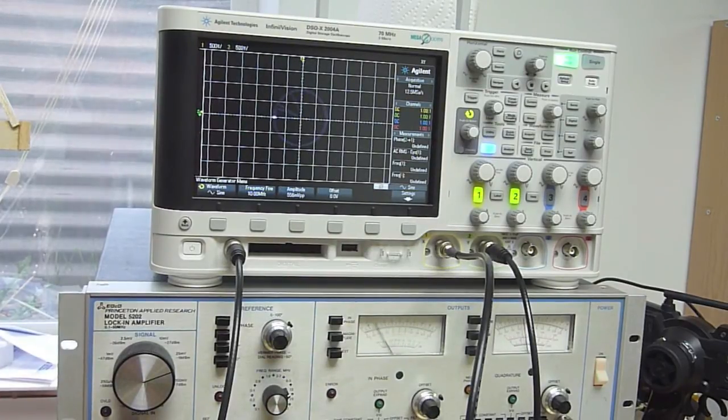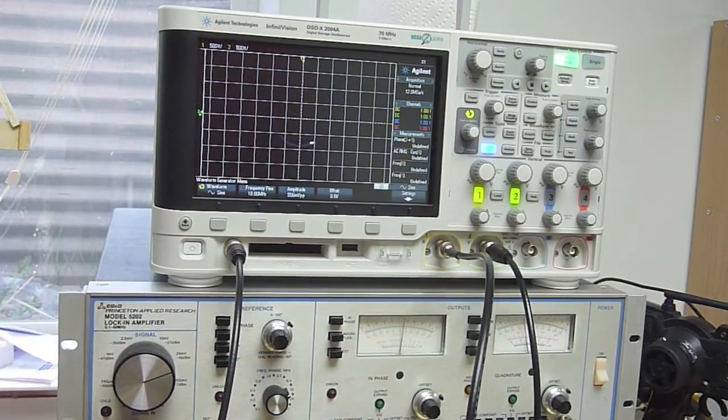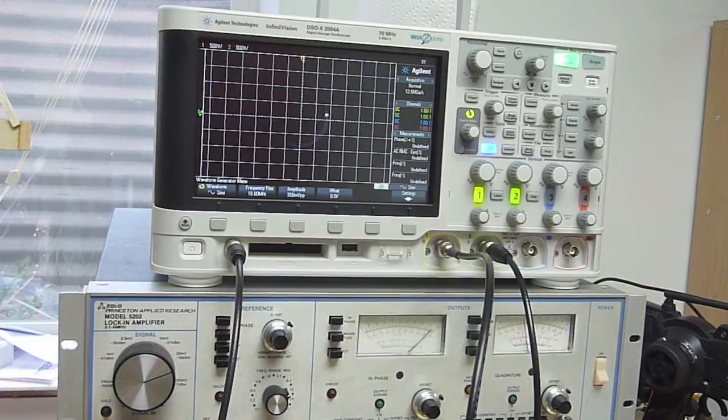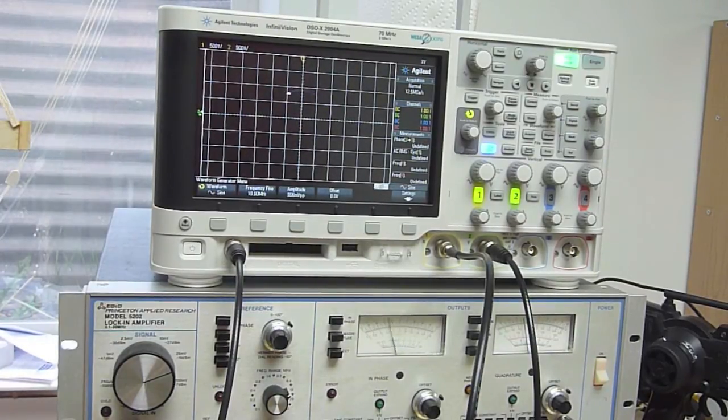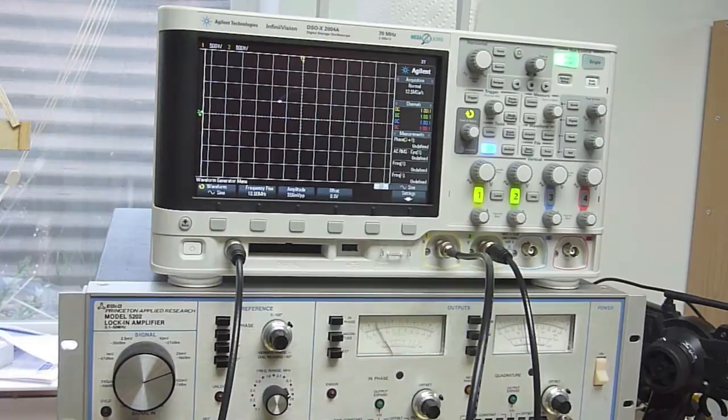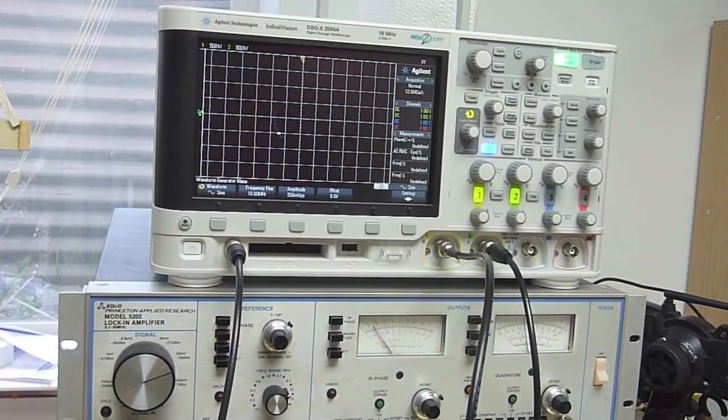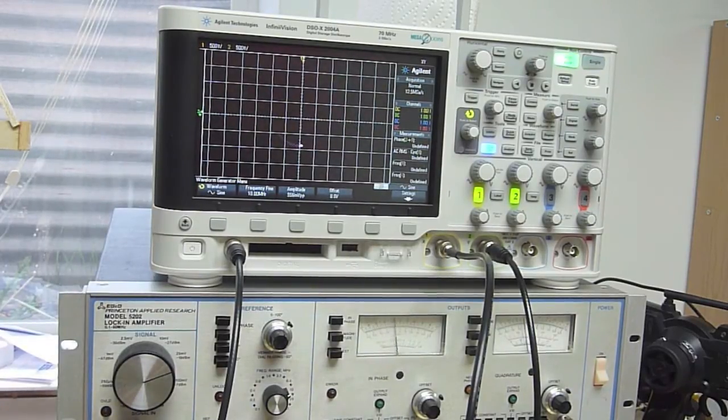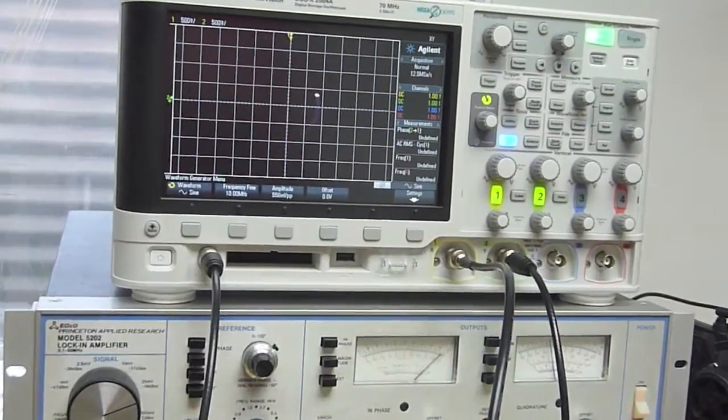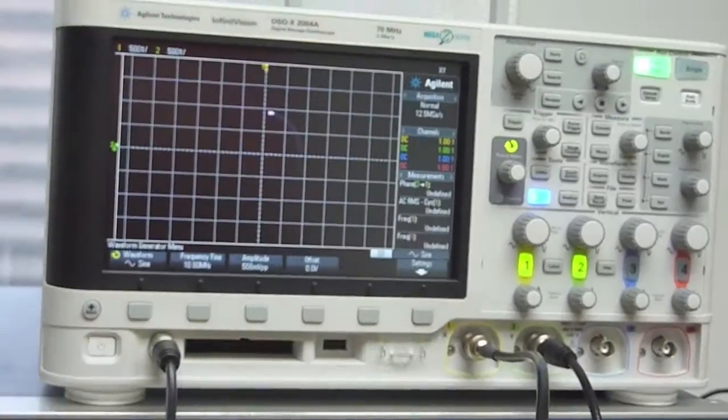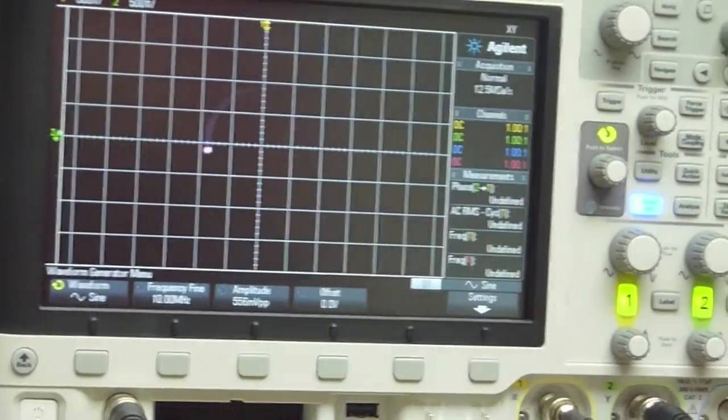So now we're at like 9.999976 megahertz on the signal generator and we're still at 10 megahertz coming out of the function generator on the scope. And you can see now that the phase relationship between the two signals is almost constant. It's drifting around ever so slightly.